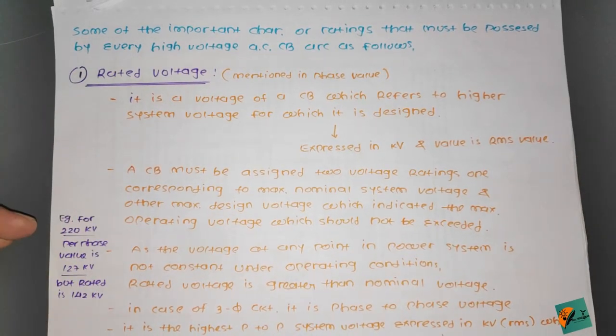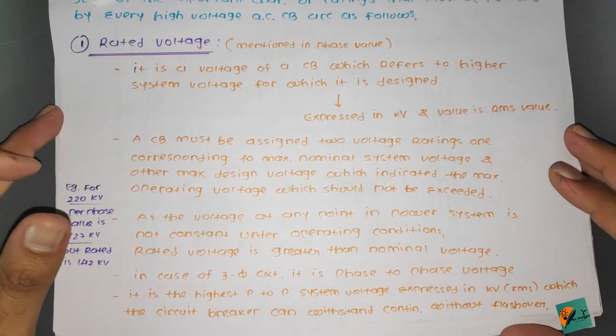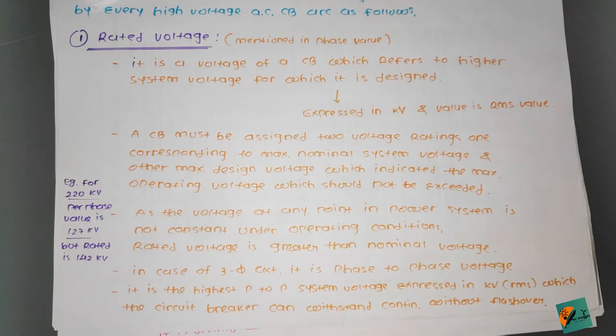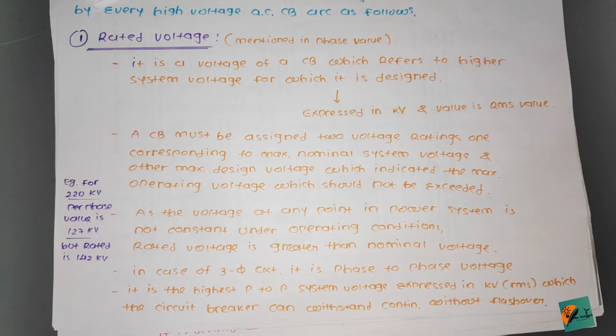Some of the important characteristics and ratings that must be possessed by every high voltage AC circuit breaker are as follows. The first one is rated voltage. It is generally mentioned as a phase-to-phase value for three-phase systems. It is the voltage of a circuit breaker which refers to the higher system voltage for which it is designed, expressed in kilovolts as an RMS value.